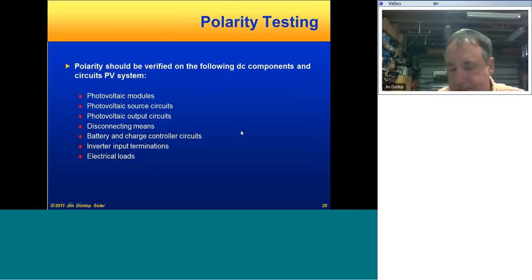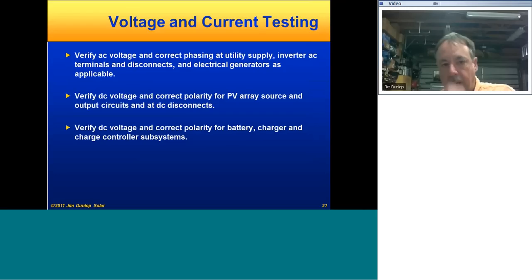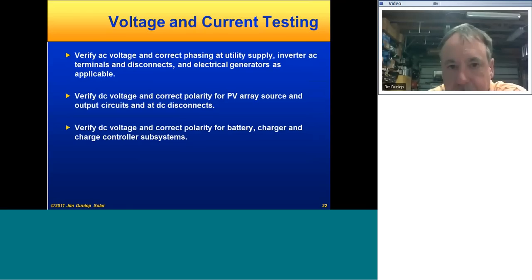Polarity testing, obviously, is done in conjunction with voltage testing. Verifying proper polarity of modules, source circuits, output circuits, disconnecting means, terminations, battery controller circuits, inverter input terminations, all that. For voltage and current testing, we want to verify correct phasing at the utility supply for three-phase systems, the AC terminals and disconnects, electrical generators, and verify DC voltage and polarity in all the DC circuits, as well as any DC utilization equipment in the system.